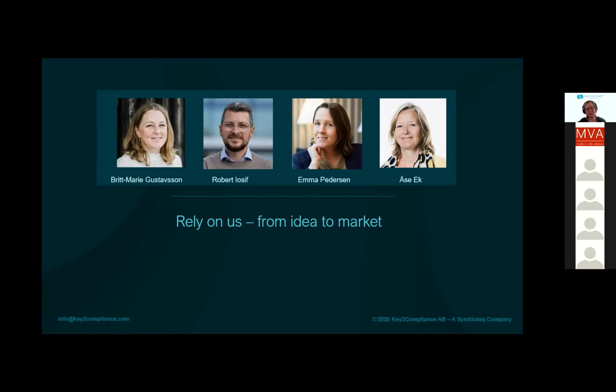So all pieces of communication must be consistent, and it also means that one of the things you may do is to be a little bit more specific in defining your intended use, thinking about whether you addressed everything from target population to user environment to restrictions on combination with other devices, environmental factors, how long you can use the device, in which tissue, and so on. Your intended use should be specific enough so that this cannot deviate. I hope that answers the question.